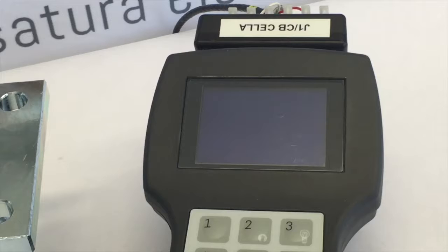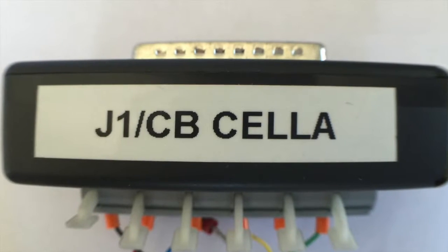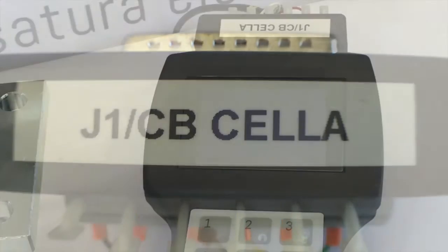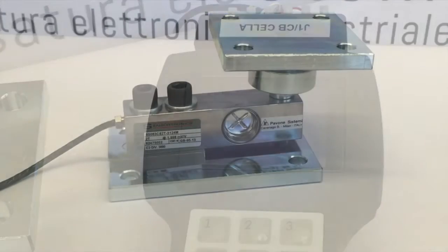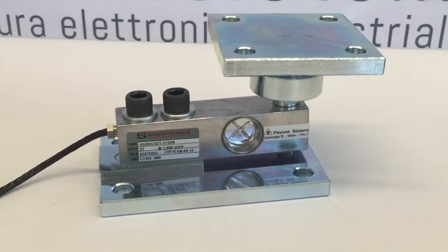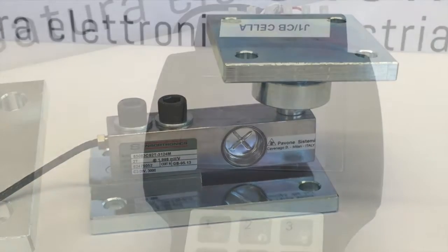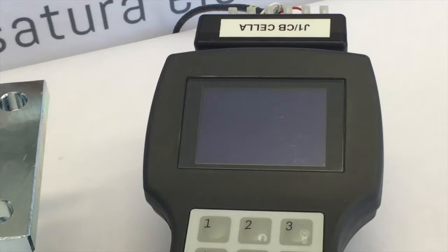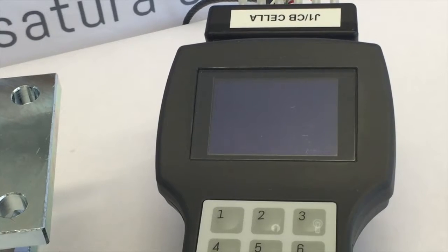Hi, today we will see how to configure our tester 1006 equipped with J1 CB CELLA connector, connected to a single cell. This will let us test the load cell. The first step is to take note of the capacity of the load cell, its sensitivity and the impedance. These data are reported on the attached certificate.